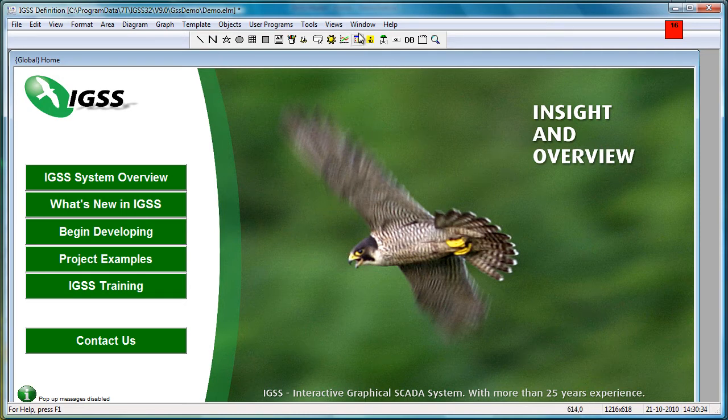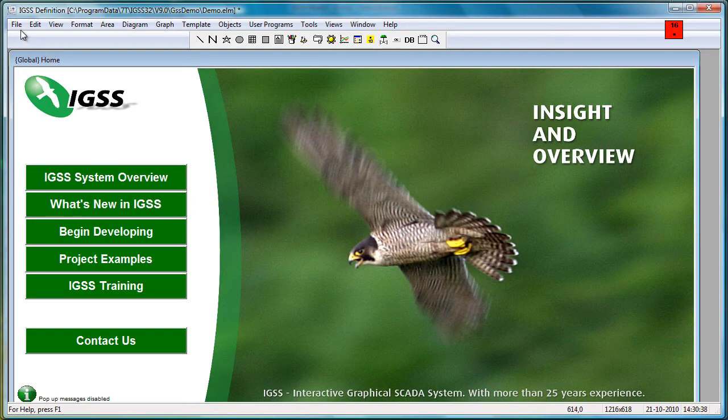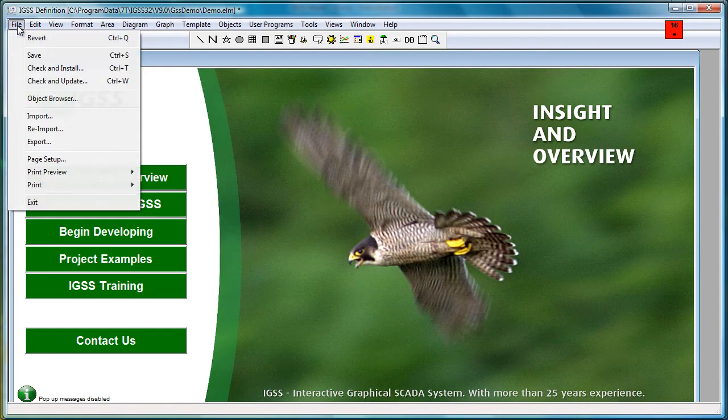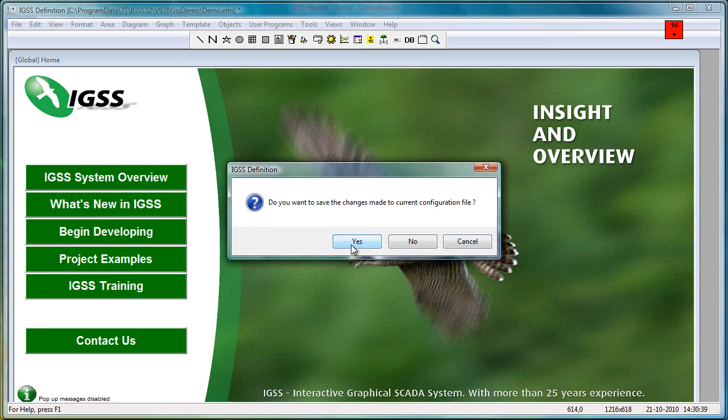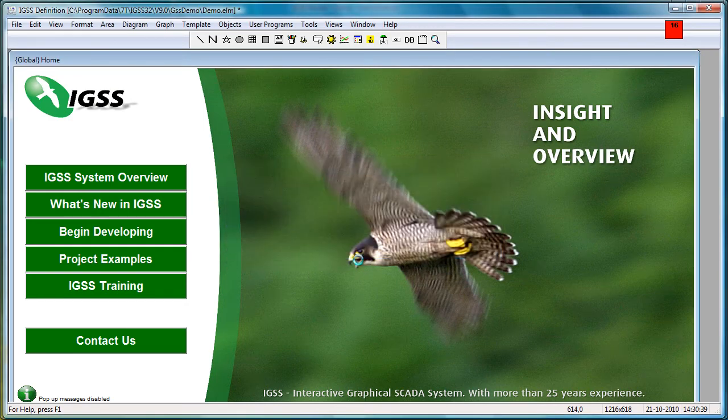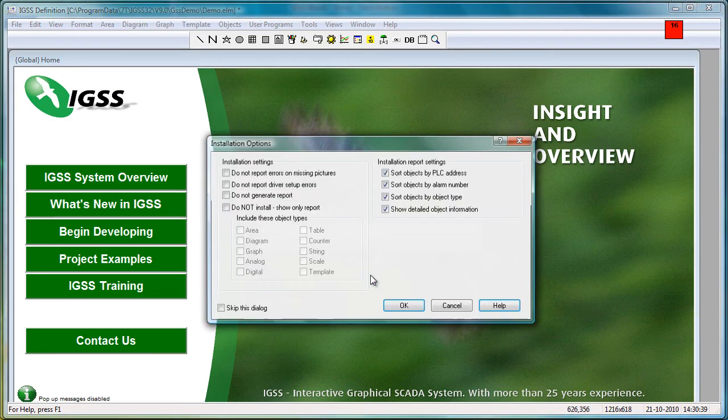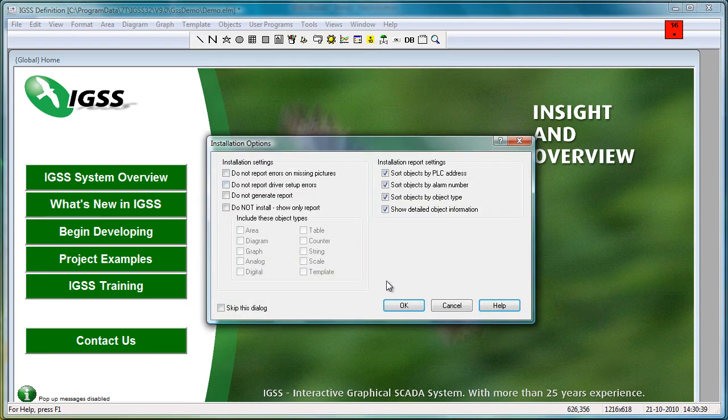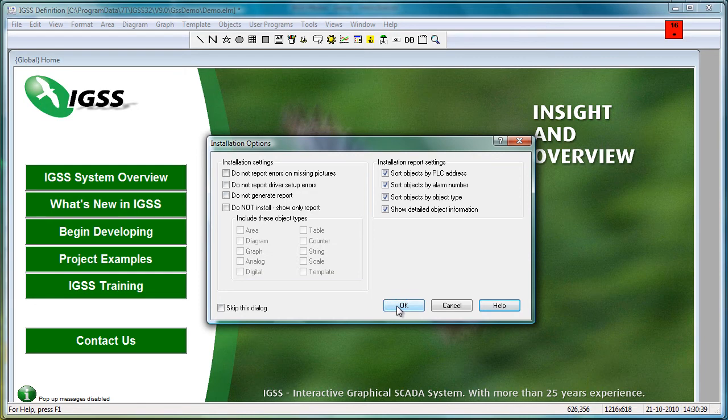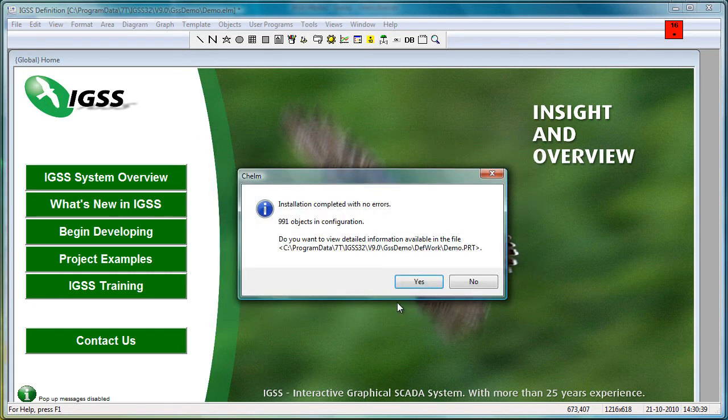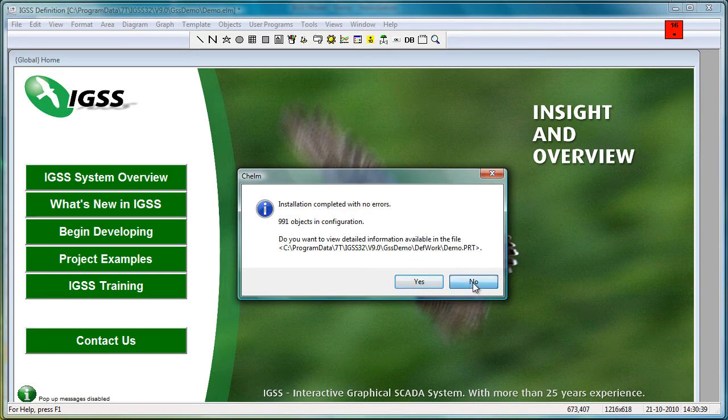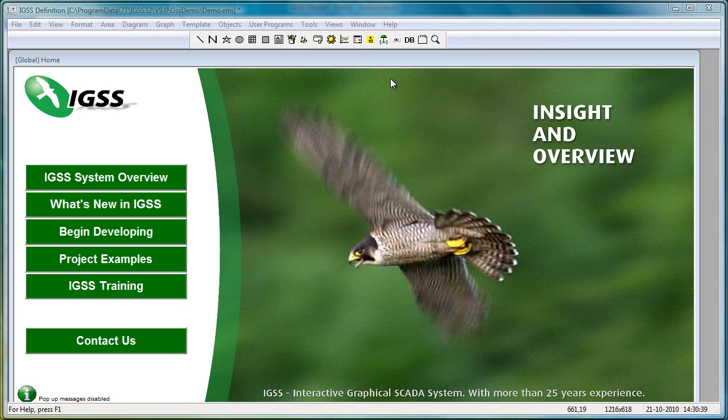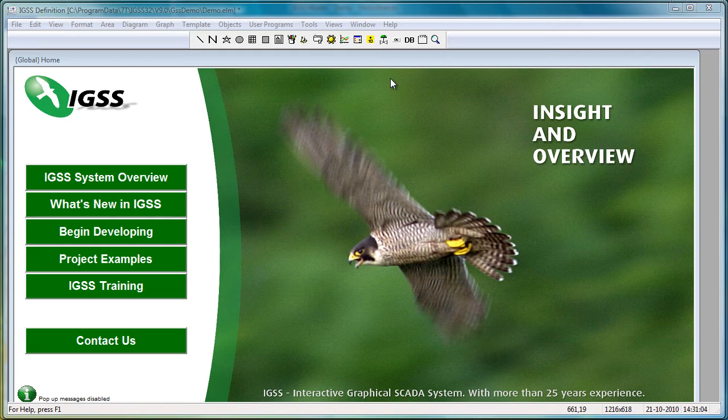In order to do that, we need to install it or compile it into the project. So we go File, Check and Update. We say yes to save the changes. We click OK in the Installation Options dialog box. And at this dialog box we say no, because we don't want to look at the report. But we can see that it's completed with no errors, which is fine. So we click no, and the project is now updated automatically.